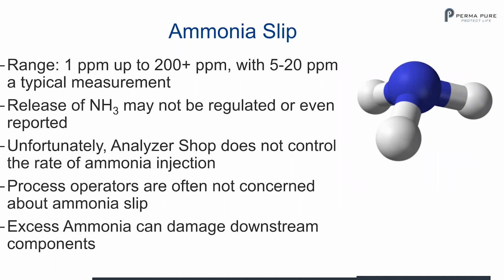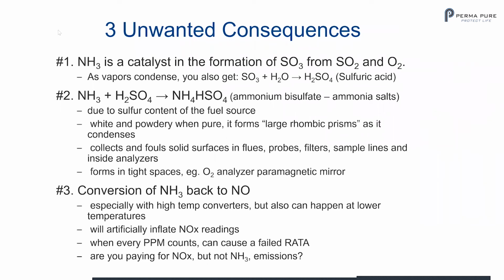Typical ammonia slip can be 1 ppm up to 200 parts per million, with 5 to 20 parts per million a typical measurement. The release of NH3 might not be regulated or even reported. And unfortunately, the analyzer shop does not control the rate of ammonia injection. Process operators are often not concerned about ammonia slip. And as we know, excess ammonia can damage downstream components in your CEMS systems. Here are some unwanted consequences of excess NH3. You can form acids, like we've shown before. You can form ammonia salts, and you can convert the NH3 back to NO and throw off your readings. All of these are unwanted consequences of ammonia slip.